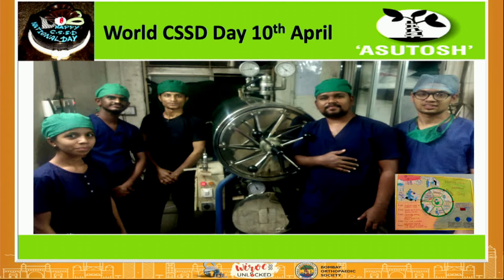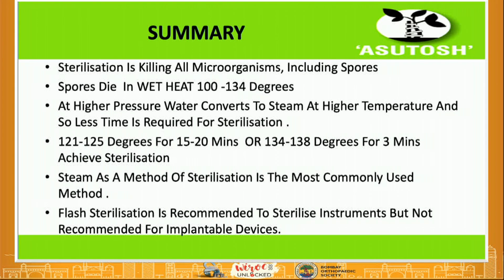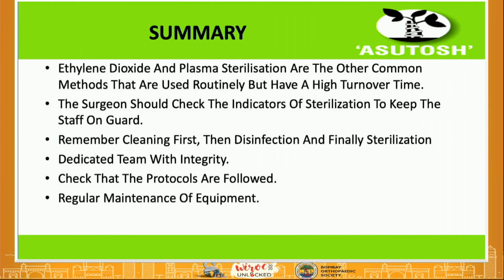Now these are our background heroes. They have to be given adequate importance. It's a very depressing job sitting behind. And World CSSD Day is the 10th of April, coming next month. So to summarize, remember that between 120 and 134 degrees, depending on the temperature, adequate time should be used. Steam is the most common method. And flash sterilization should only be done for instruments, not for implants.